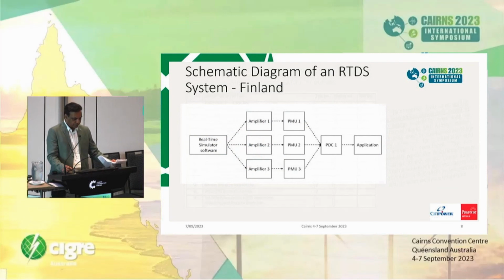The next example is from Finland. On the left-hand side, you can see an RTDS simulator, and then through amplifiers it goes to PMUs, then to the PDC, and finally to the control center or to the application. By simulating measurement values from the RTDS and checking them on the application software, they ensured that the measurement accuracy is within the international standard IEEE C37.118.